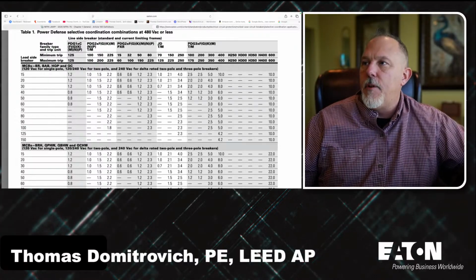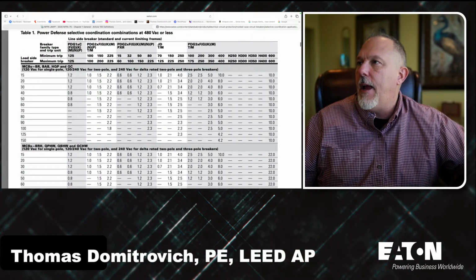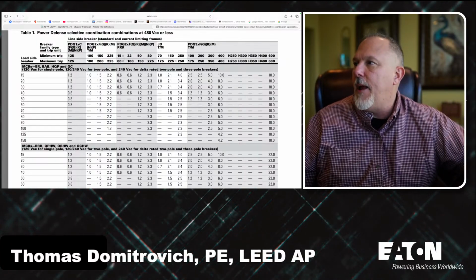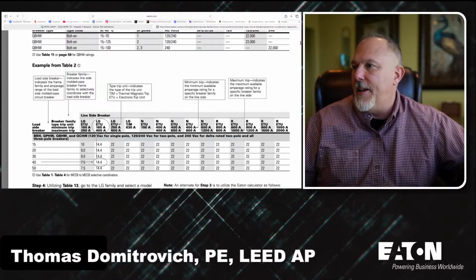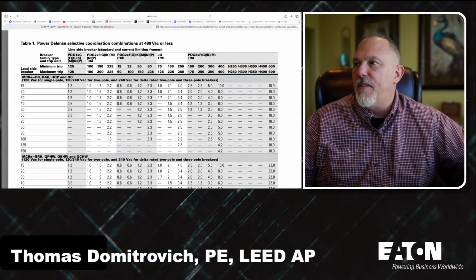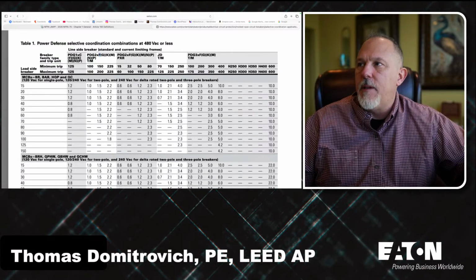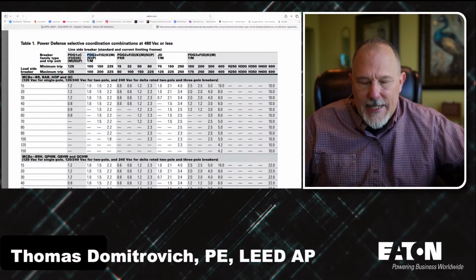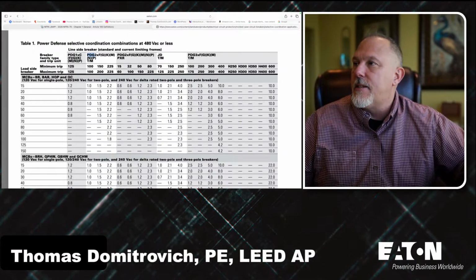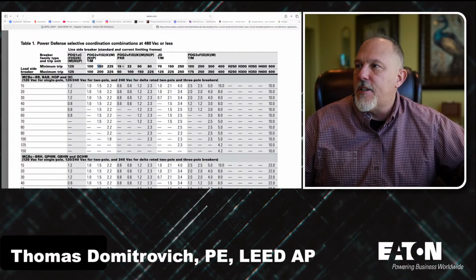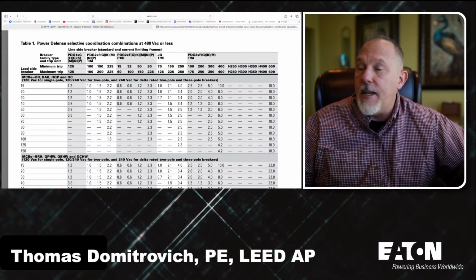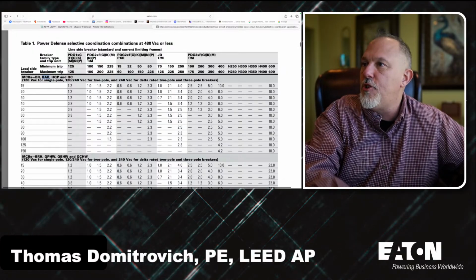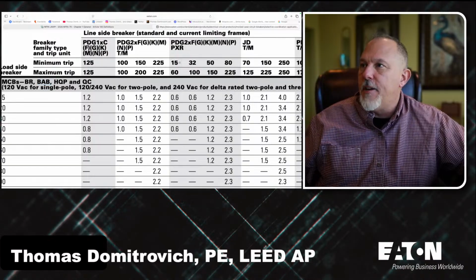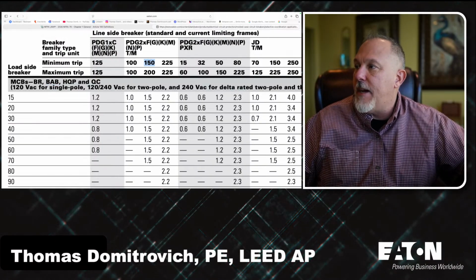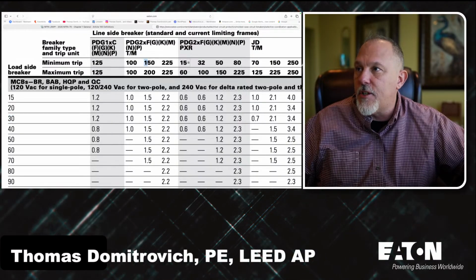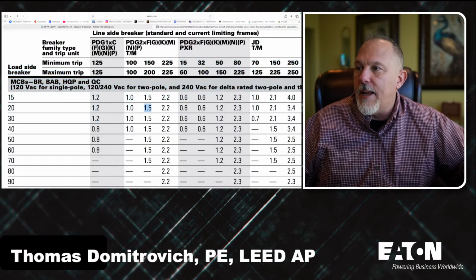So I have the upstream breakers on the top, the line side up top, and the load side down the bottom. So we said that we had an FD 150, which is there's my F frame, but it's now a PDG2. So they changed the information. I had 150, so there's my 150. There is my BAB. All right. I'm going to zoom in. So there's my 150, and there's my 20 and my 30. And when I come down from the 150 to the 30, I got 1.5.